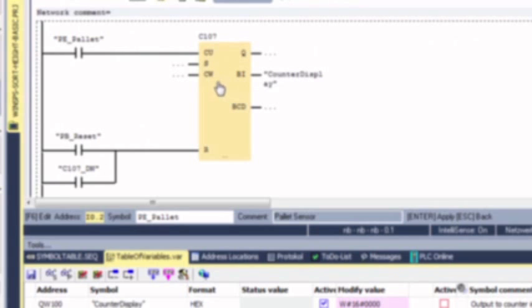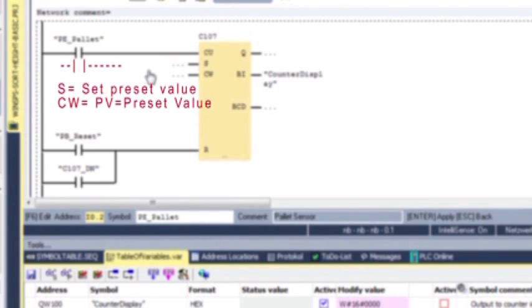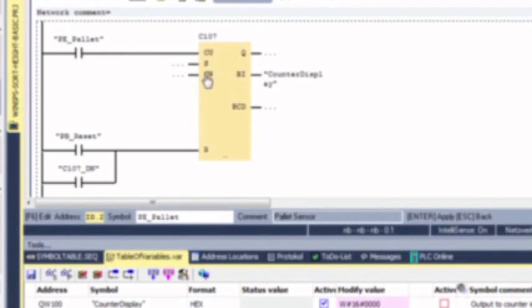Siemens has the ability to put a preset in the counter, but you have to put a rung here with an extra bit — and it is a bit, pun intended, confusing. So we don't use this. Instead, we write our own compare statement below that to perform that functionality and put our preset in the counter.